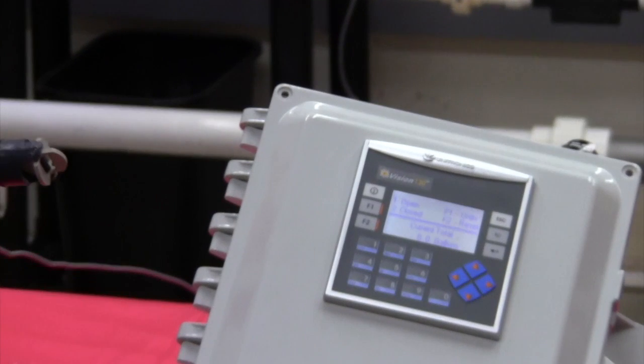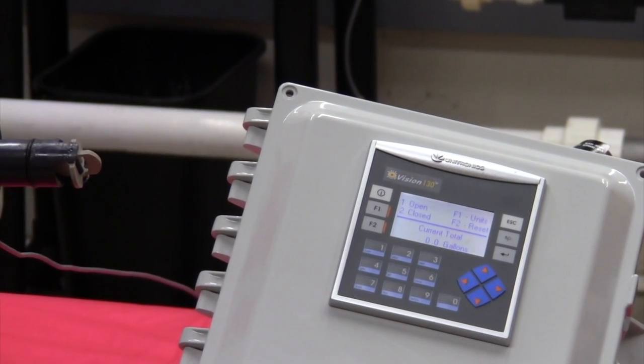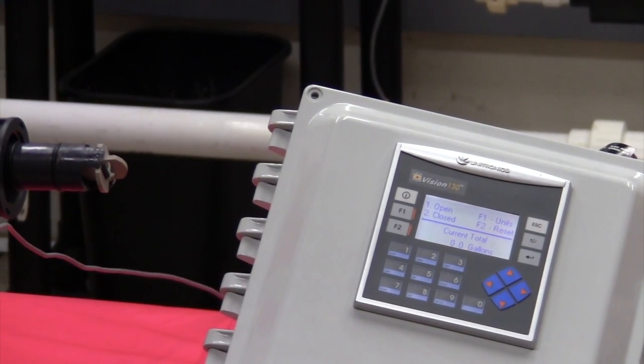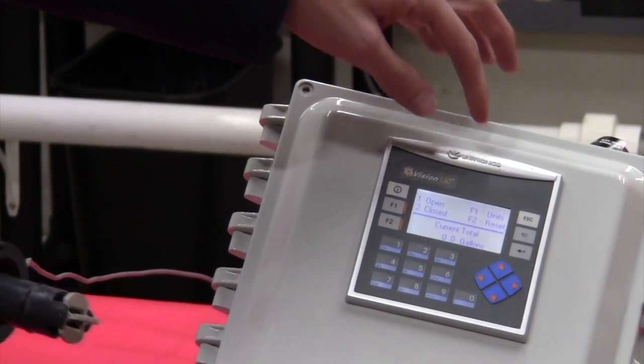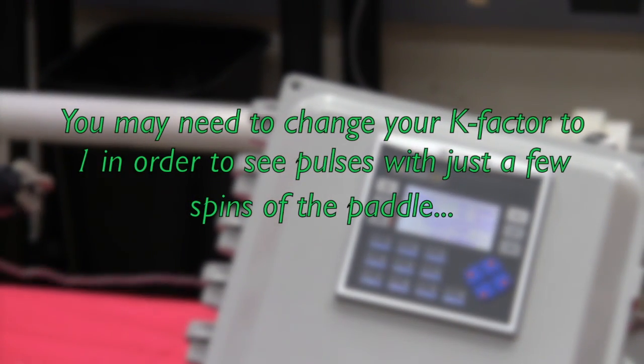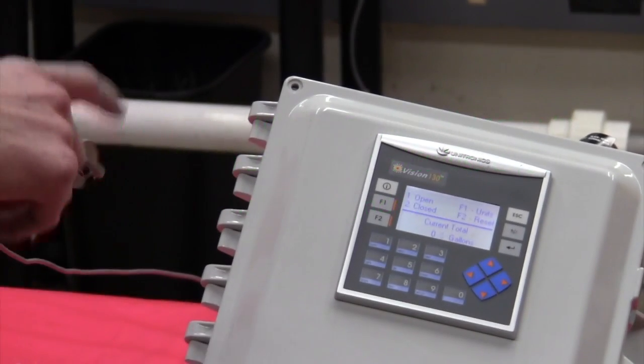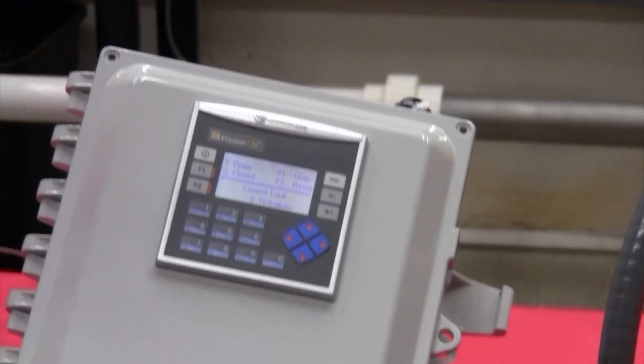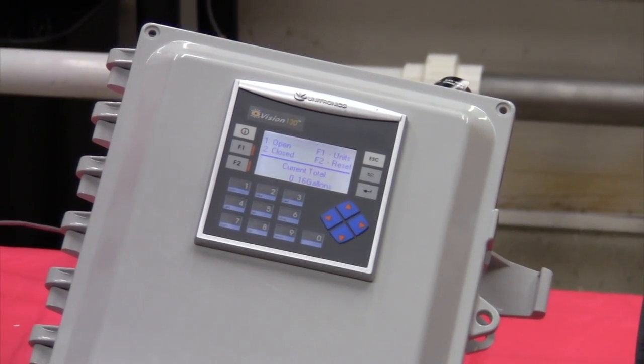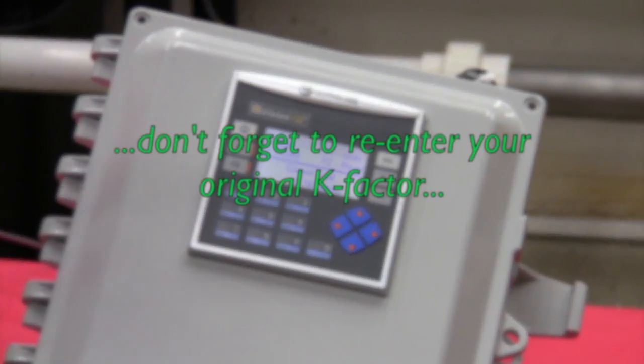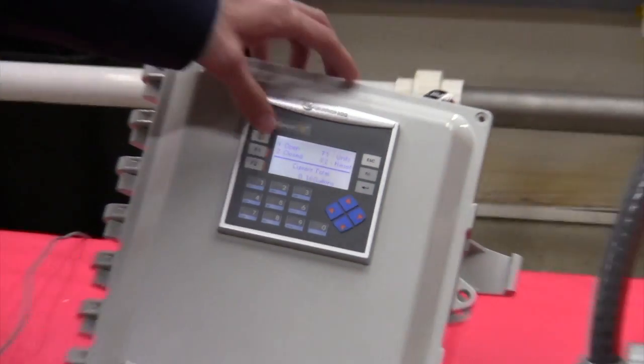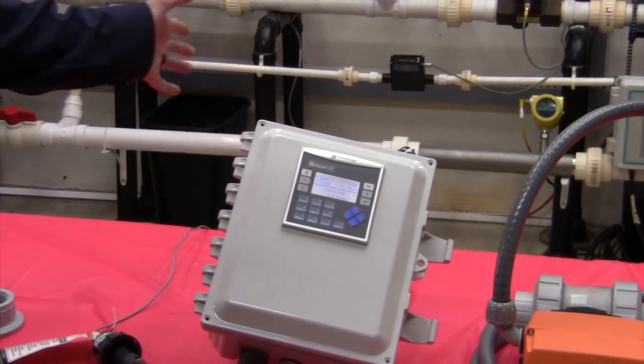What that's going to tell me is that I'm both outputting a pulse from the flow meter, and the display is seeing the pulses coming into it via the wire. So if I give it a spin, you can see the totalization happening right there. That's great. I know my flow meter is outputting pulses, and I know that my display is receiving pulses. If I hit F2, I can reset that back to 0.